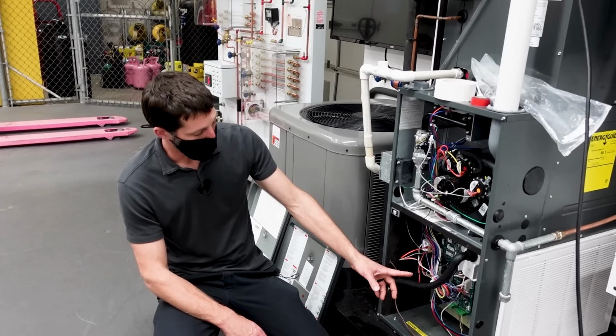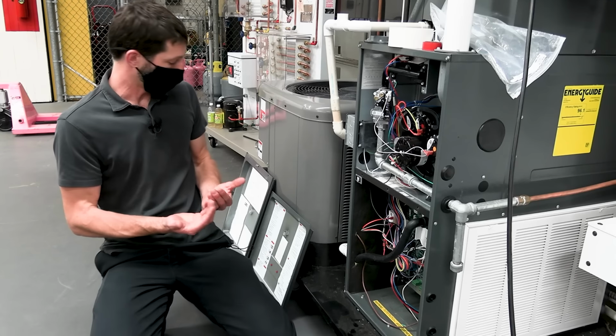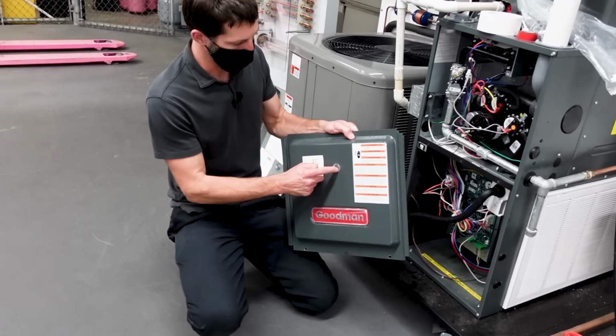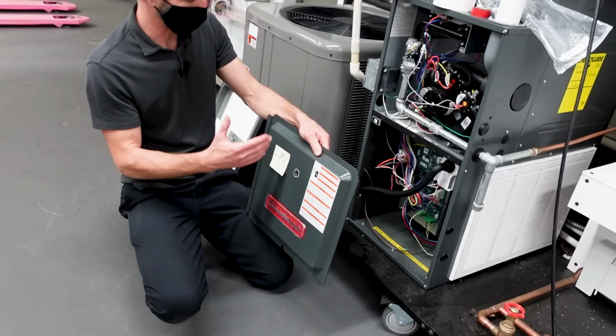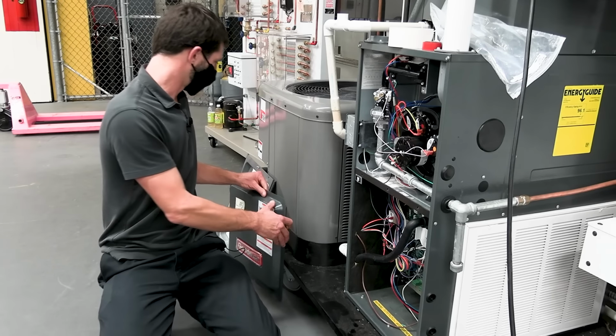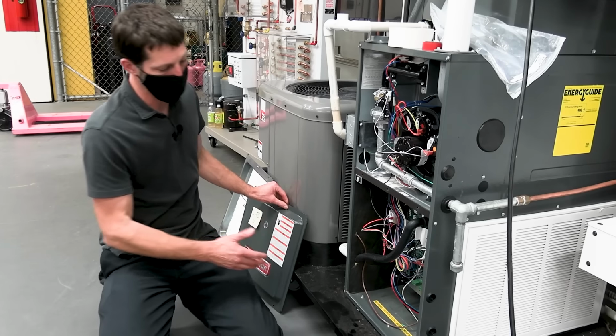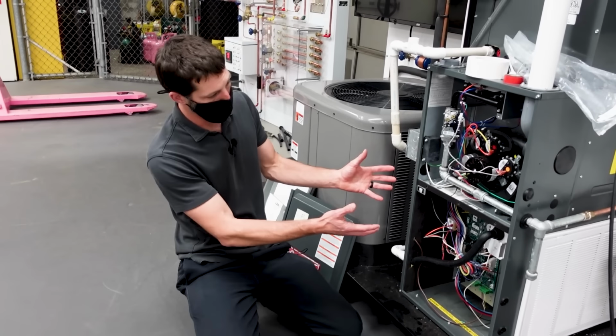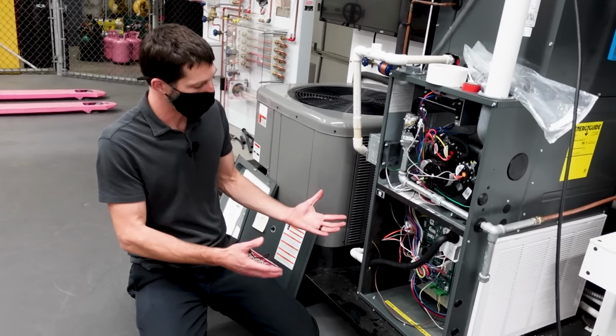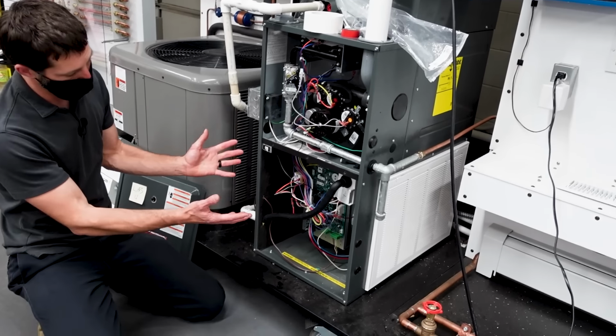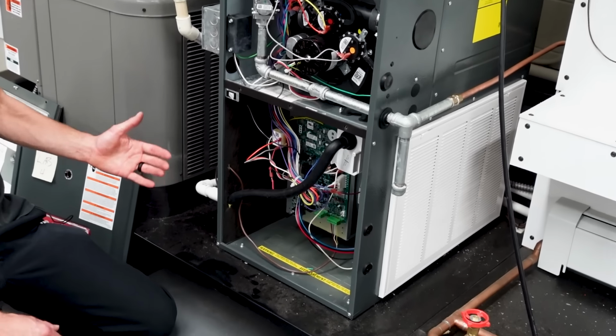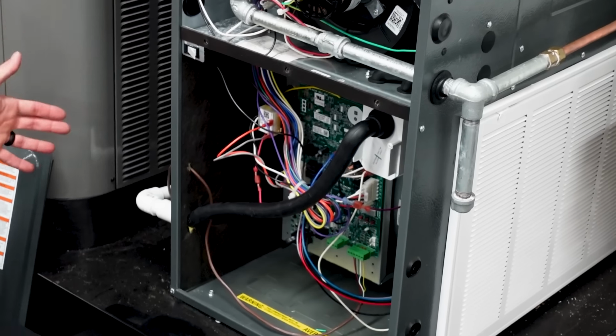There's an LED status code, so if you're not sure how to recall the status code, you want to look through the window first before taking the door off and count the status codes, whether it's a short flash, long flash, or a combination of both, depending on the unit. You want to write that down before taking the door off. You can recall the status codes of all the errors that have occurred on the gas furnace. You just have to read the manufacturer's literature on how to recall it.